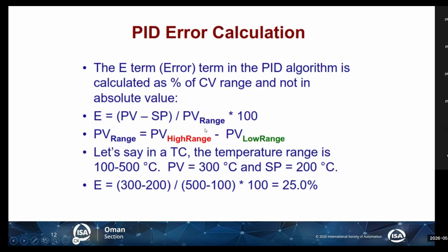Why is this important? We have seen this a lot in many plants. Some people will say that the controller is not working properly, performance is very, very bad, so they will ask for tuning. One of the most important things before you tune the controller is to check whether you have the correct range on the instrument or not. You should have the correct range on the field and on the DCS, because this equation exists in the PID algorithm. If the range is wrong, then your error is not accurate, then your PID action is not accurate, and then your PID performance is bad, and tuning will never help you.